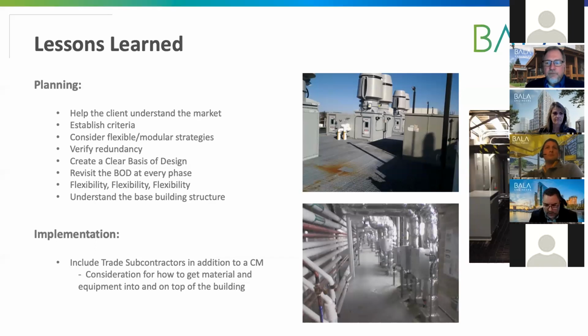One thing to tag onto that too, I'm wondering if that has to do with commissioning. Definitely with a laboratory space, it tends to get commissioned by a third party just to verify the systems are performing as intended. But of course commissioning does occur even on office buildings, especially anything that's LEED-based.